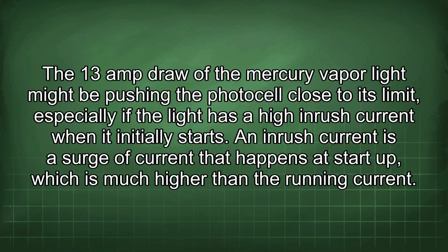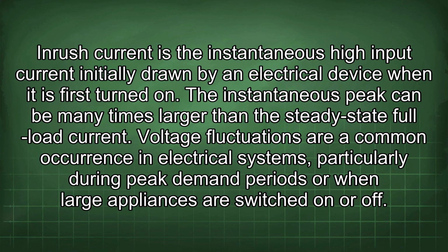The 13 amp draw of the mercury vapor light might be pushing the photocell close to its limit, especially if the light has a high inrush current when it initially starts. An inrush current is a surge of current that happens at startup, which is much higher than the running current. Inrush current is the instantaneous high input current initially drawn by an electrical device when it is first turned on. The instantaneous peak can be many times larger than the steady-state full load current.